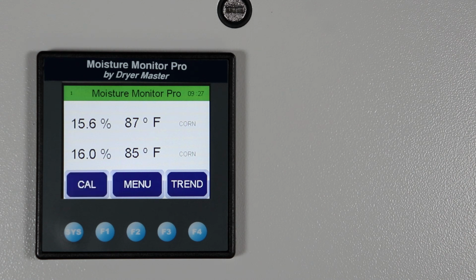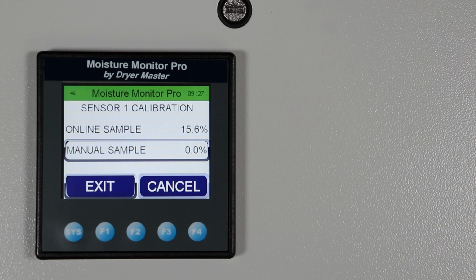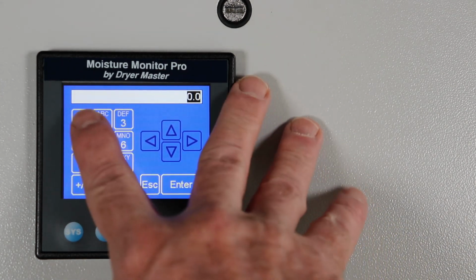And the idea here is to get good agreement and a good calibration. What you want to do is have as big a sample as you can. That's why we talk about 30 seconds. Okay, and then usually we recommend as well that you take a big enough sample, you can run 3 tests out of it and then take the average. But let's say our online sample is 15.6. Let's say your manual sample is 16.